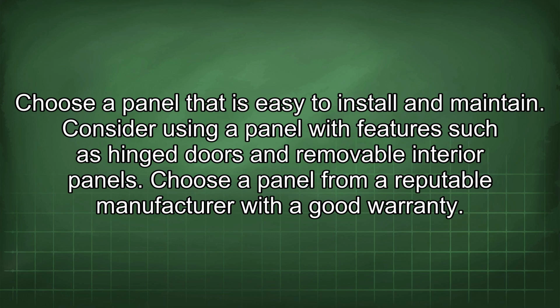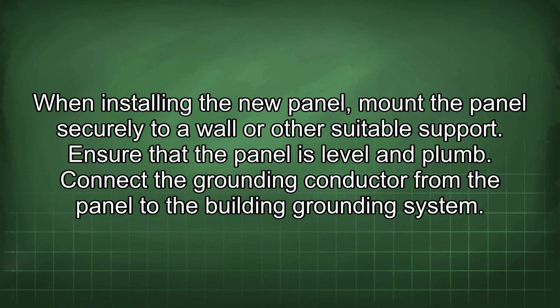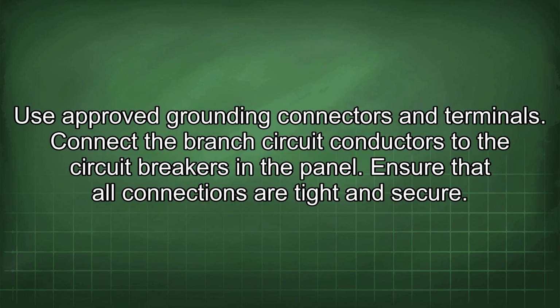Consider using a panel with features such as hinge doors and removable interior panels. Choose a panel from a reputable manufacturer with a good warranty. When installing the new panel, mount the panel securely to a wall or other suitable support. Ensure that the panel is level and plumb. Connect the grounding conductor from the panel to the building grounding system. Use approved grounding connectors and terminals.